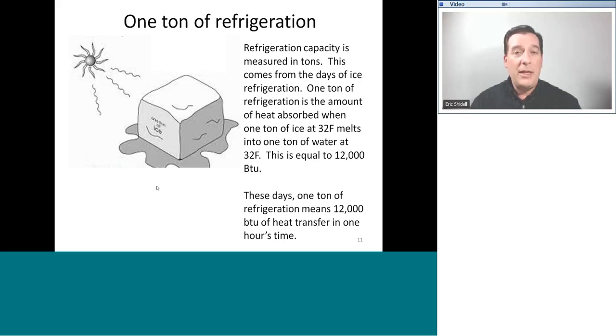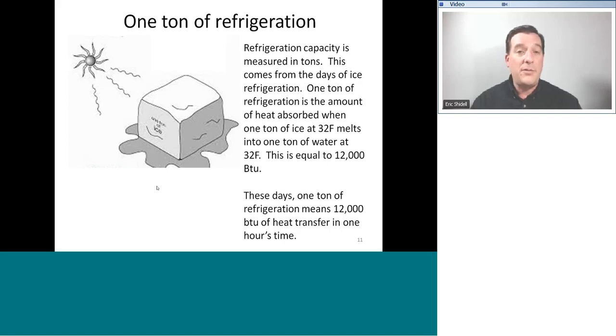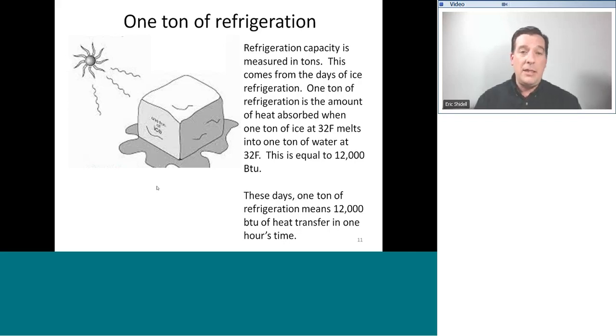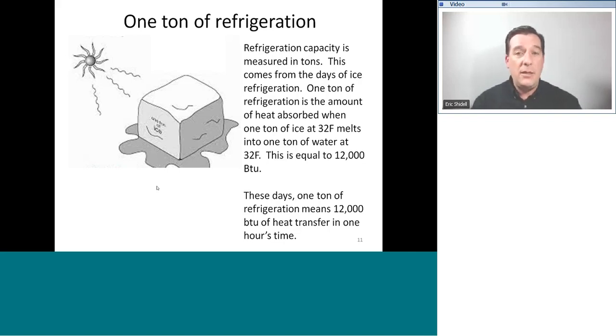In commercial applications, they don't necessarily say 'three ton' or 'five ton' in the model numbers. They'll have a number that indicates thousands of BTU per hour. For example, if a commercial unit has 240 in the model number, that means 240,000 BTU per hour — that would be a 20-ton air conditioner. That's how the whole ton thing works. It's based on ice refrigeration, and modern-day refrigeration seeks to duplicate the exact same process.